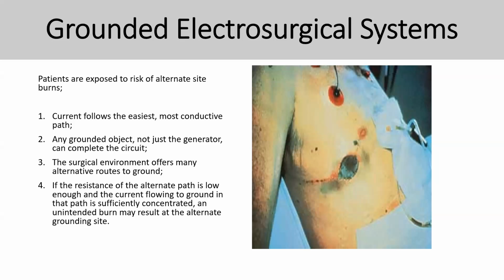So what happens is, if you've got ECG electrodes, and the electrosurgical unit patient plate is not attached properly, or the single-use patient plate may be broken or something like that, the current is going to find a different part of the ground line. So the ECG can be one of the points that it can pass through, or the bed itself. So for example, your OR table. If your OR table is grounded, and the ground of the OR table is much lower than your ESU ground, it is going to find that path. So basically, these are risks for the patient actually.